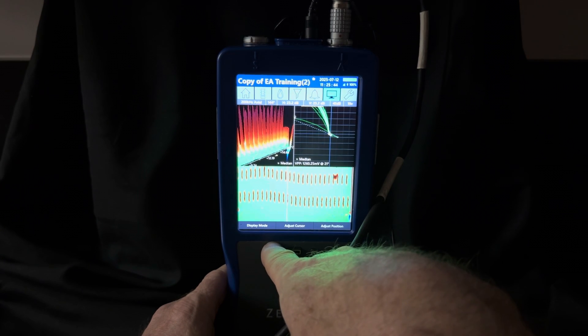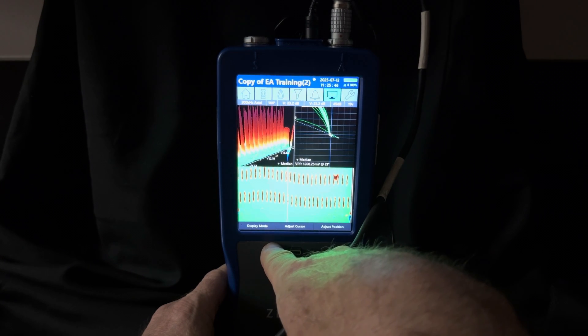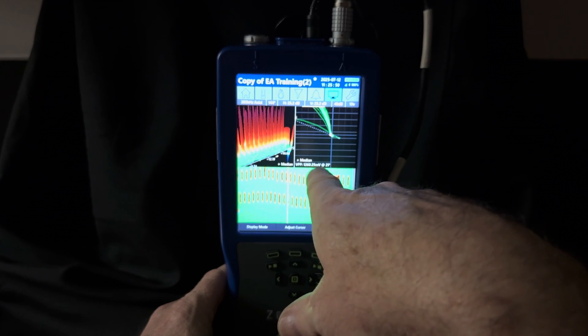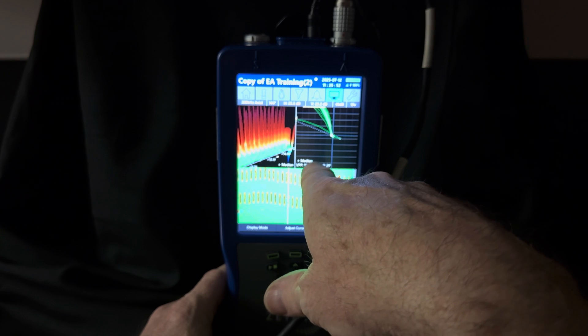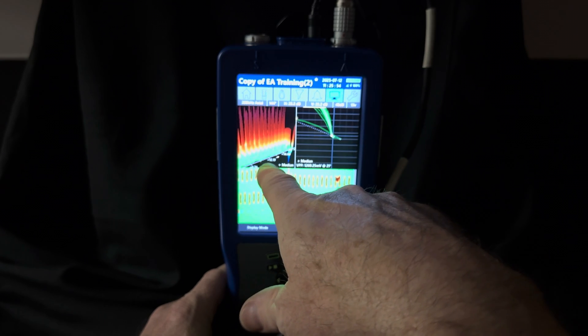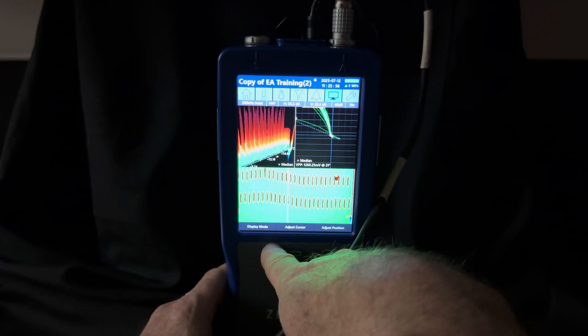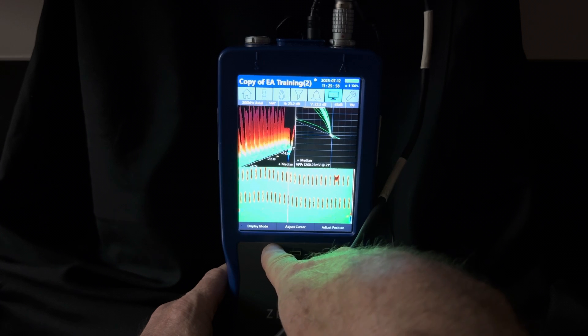If you're using like an array weld probe, that's got plus point coils in it, and the sets of array coils. So you kind of have to pay attention to what coil pairs or coil is being displayed, because that's going to help you evaluate the data.